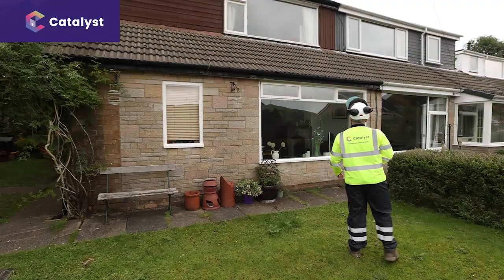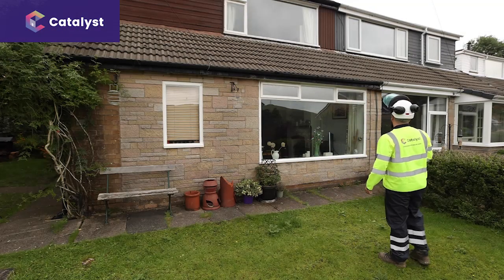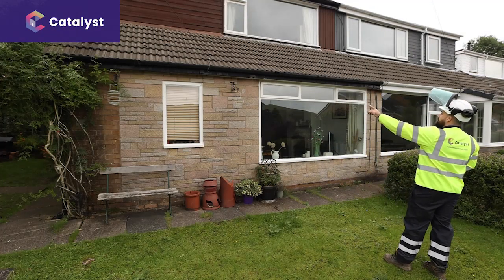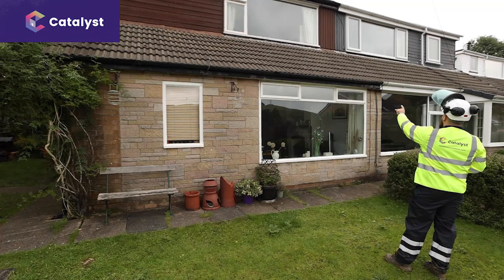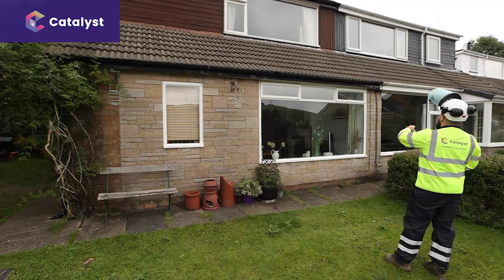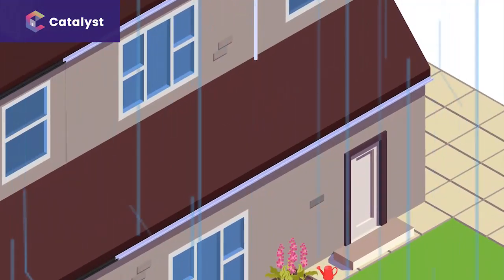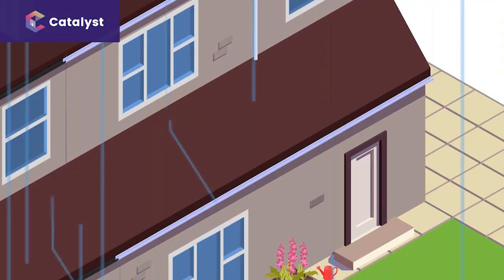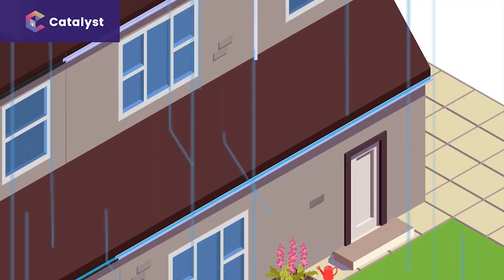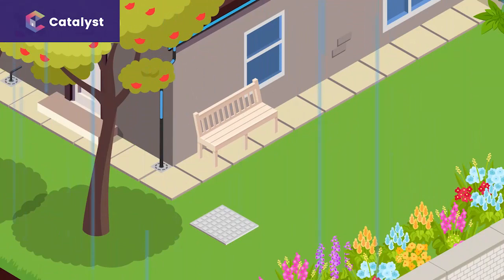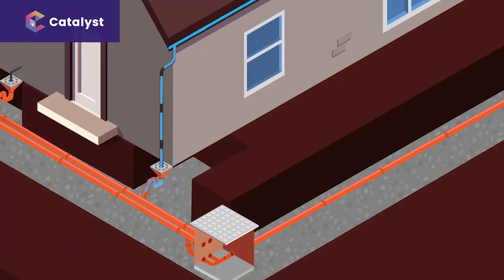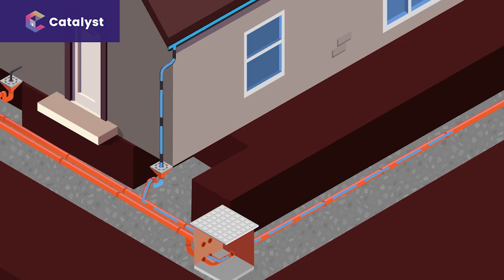Another important task is to check the gully connections. This establishes where the water it takes comes from and who derives the benefit. As we can see, this is a shared gully — it takes water from our customer's gutters and those of their neighbours. Both properties derive benefit from the same drainage system. Therefore, as it's shared, it's the responsibility of the local water company to maintain serviceability.